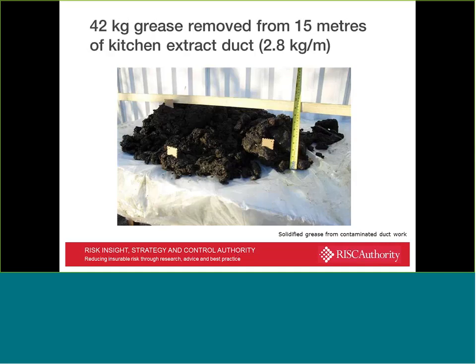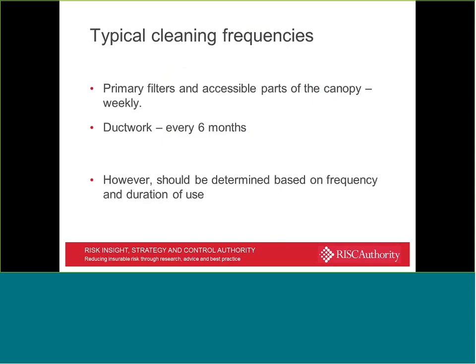And that's a photograph that I'm sure some of you have seen before. It's just a nasty lump of grease removed from just 15 metres of extract ductwork. 2.8 kilograms per metre of ductwork were extracted to form that level of grease. And of course, there is a significant fire load maintaining that.